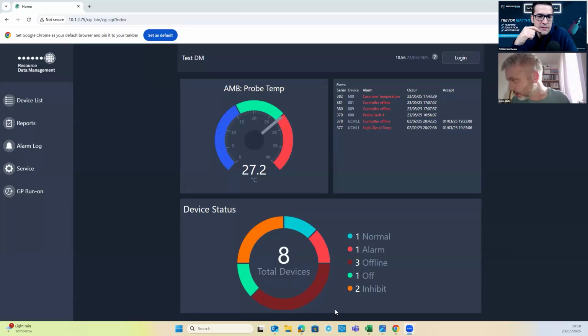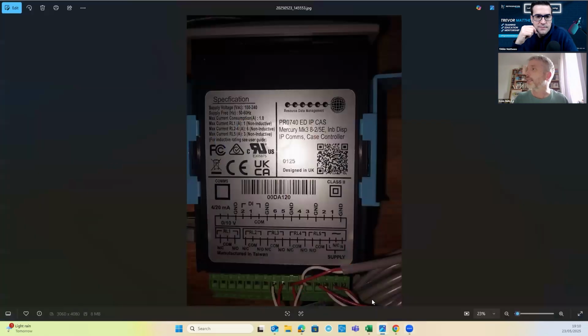So just to illustrate what I was talking about before, that is an IP controller, because it says IP on it. They make it pretty simple in that regard. And obviously they very handily give you a wiring diagram on the back where everything needs to go. A couple of things to point out on here where it says NC. On the mains, NC means not connected, not normally closed. Don't put anything in there.